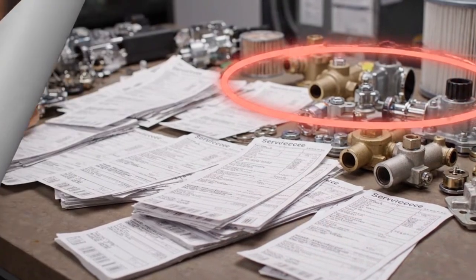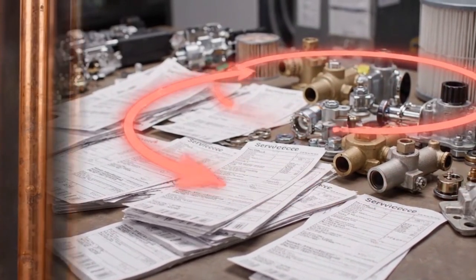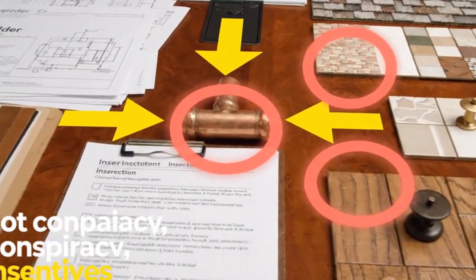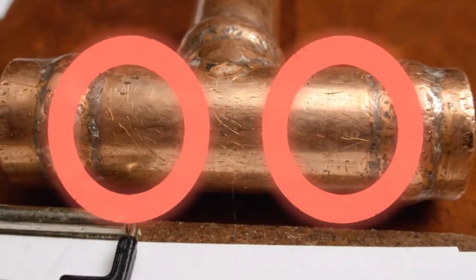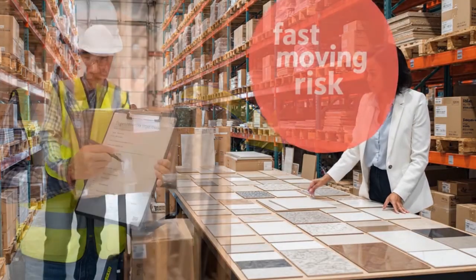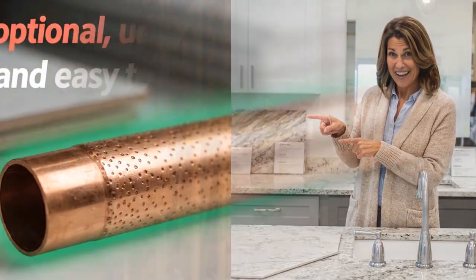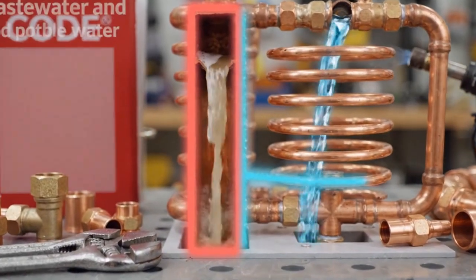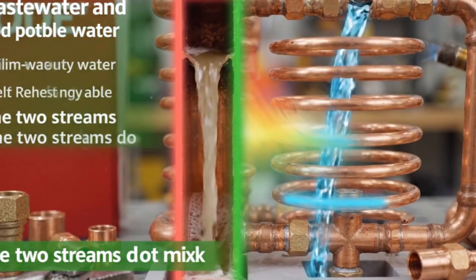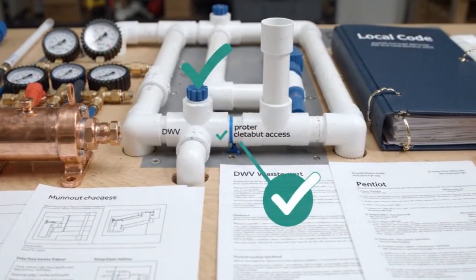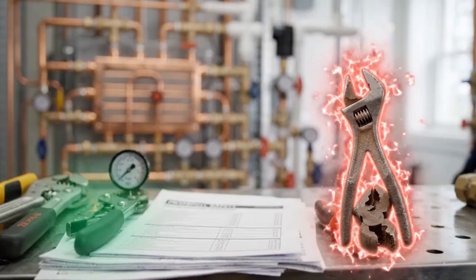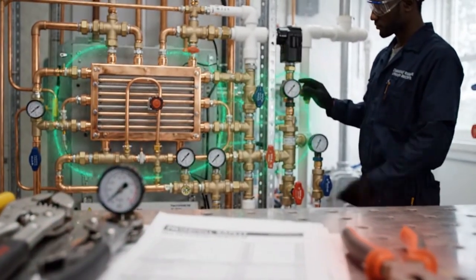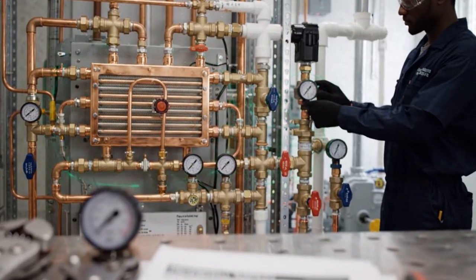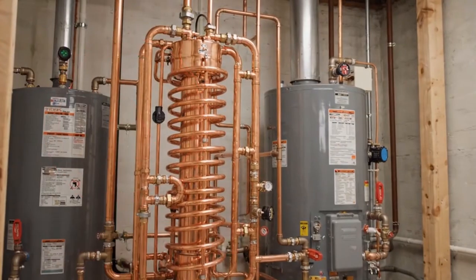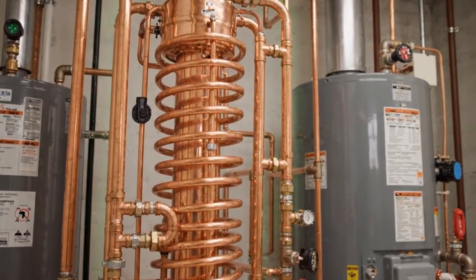Then there is the code and contractor problem. Drain water heat recovery deals with both wastewater and potable water. Even though the two streams do not mix, the system still sits at an important boundary inside the plumbing system. That means installation has to be done correctly. The heat exchanger has to be approved for the application. The plumbing arrangement has to meet local code. The potable water side has to be protected. The drainage system still has to drain properly. There can be pressure drop considerations, clean out and access considerations, and local inspection requirements.